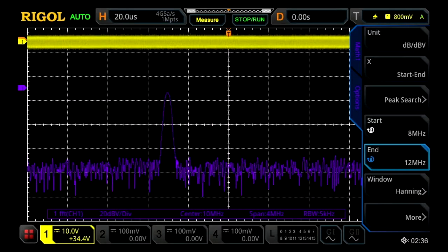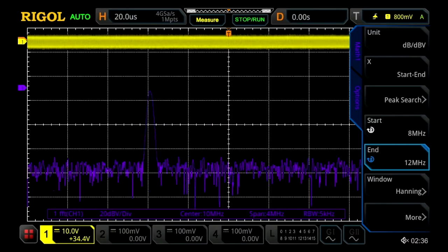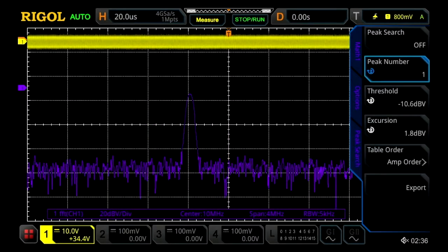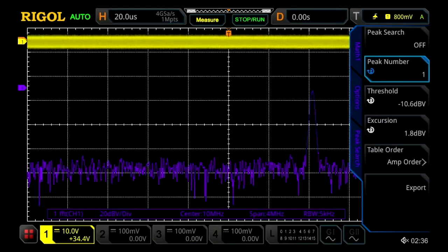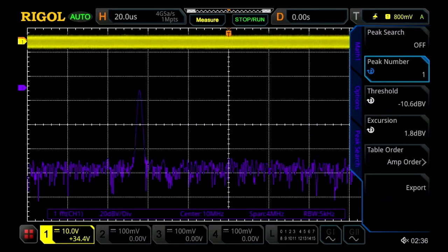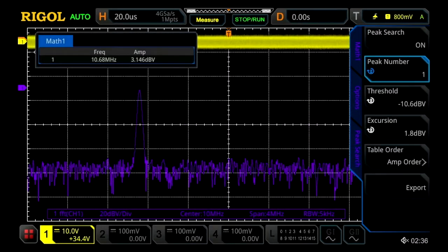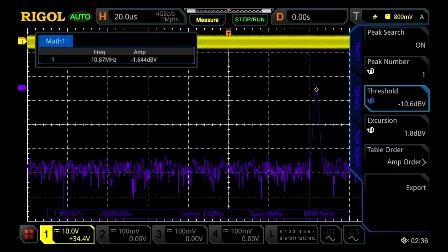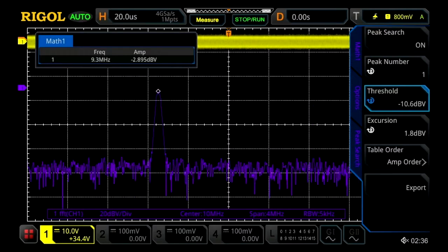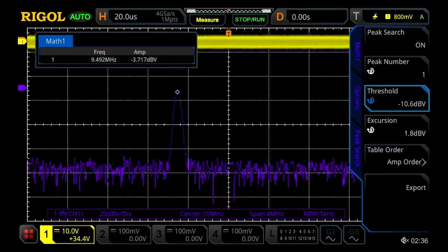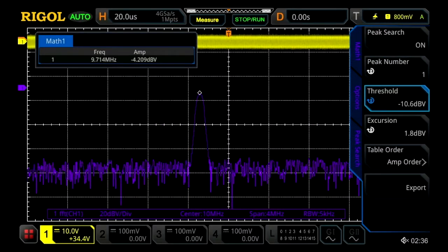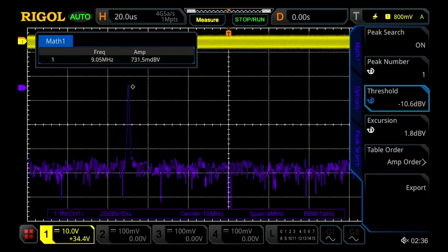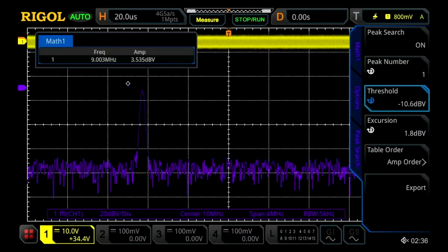Next thing we can do with this instrument is use the peak search capability to find that peak and identify it. We've got it identified already and it'll show our peak and show it move around on the screen as the signal's moving around.